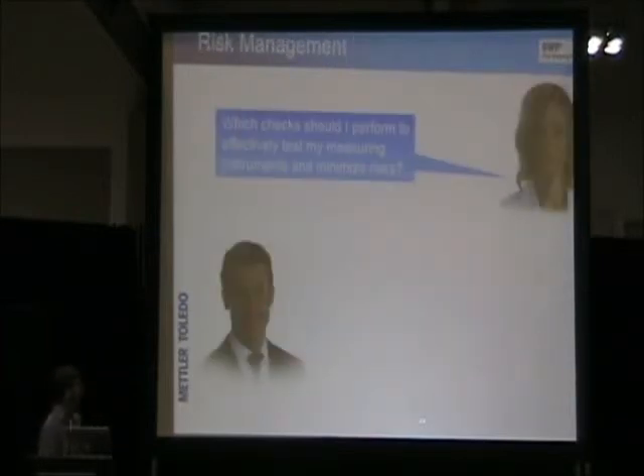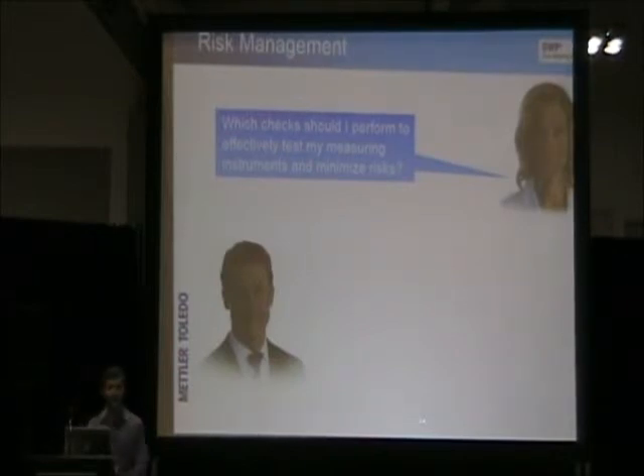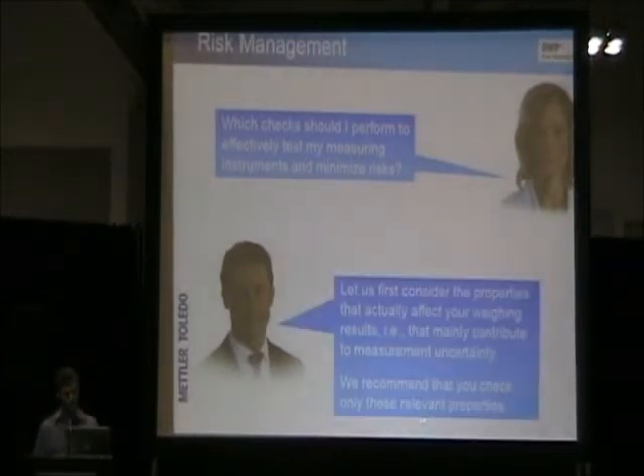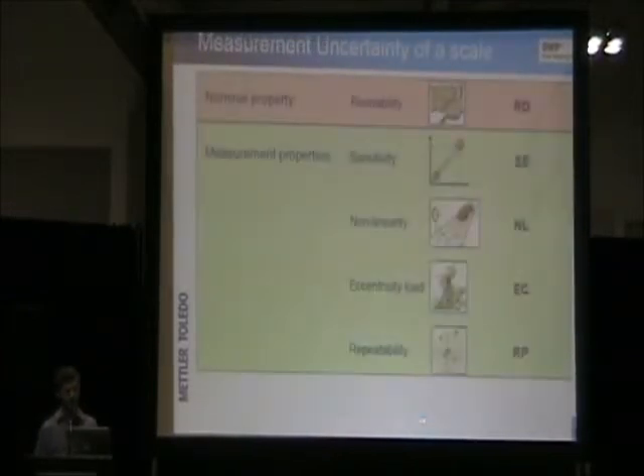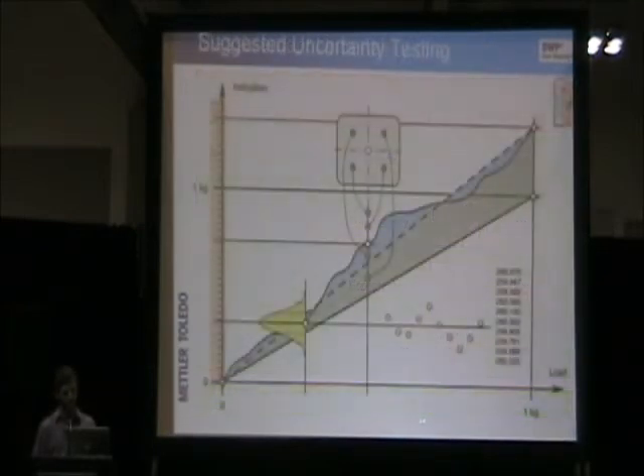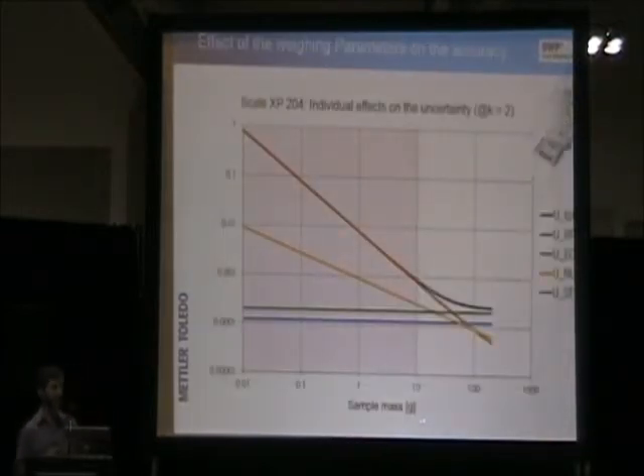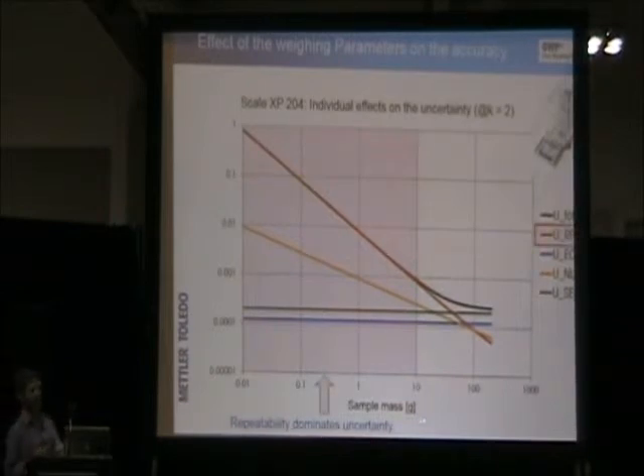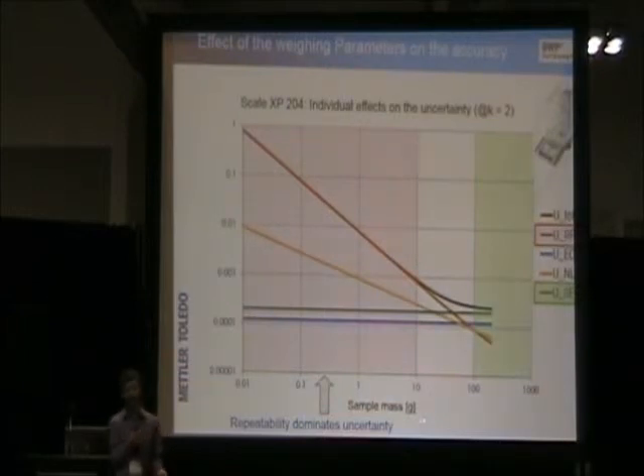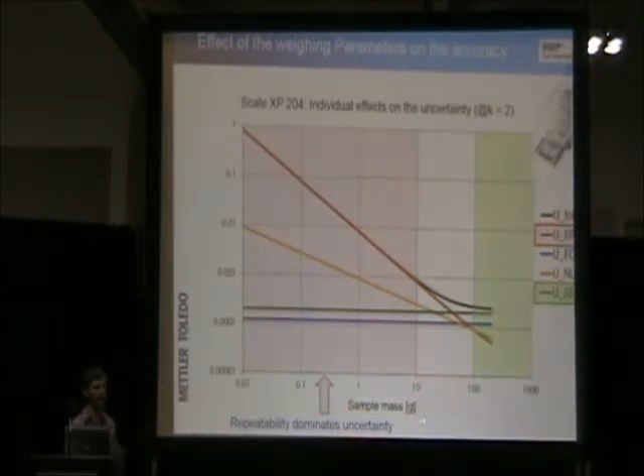So, risk management. Which check should I perform to effectively test my measuring instruments and to minimize risks? Let's consider the different properties that we went over here quickly. When you have a technician come in, he's going to test all these parameters to establish your total uncertainty of measurement. I know that we're running out of time, so I'm going to show this last slide, because this is kind of the kicker to put everything together. This is a graph of your total uncertainty of measurement. This black line represents the total uncertainty of measurement that encompasses all four parameters of uncertainty and your nominal parameter of readability.